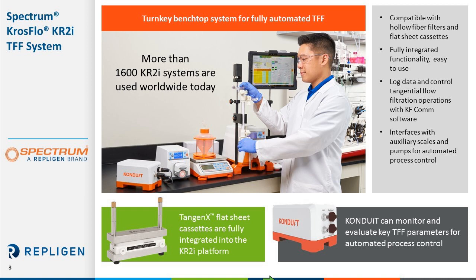The KrosFlo KR2i TFF system from Repligen is a turnkey benchtop system for TFF process development and small scale processing, and an ideal system for UFDF applications and downstream processing. The KR2i is the most economical lab scale TFF system on the market today and enables operations of both hollow fiber filters and flat sheet cassettes. The system allows for precise and reproducible control and data logging through the KF Comm control software. Today we will discuss why over 1,600 systems are in use in the industry today.